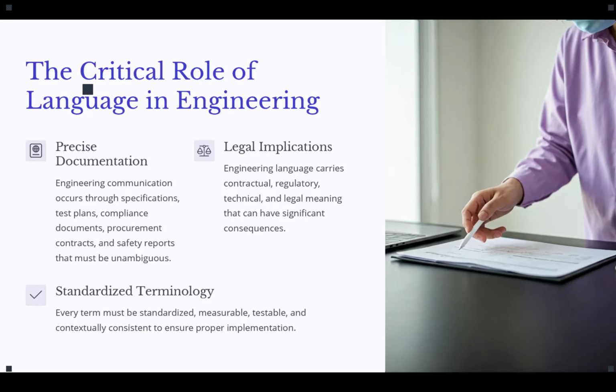Protective earth ground, which is intended to protect human safety, is one meaning. Another one is signal reference ground, which is critical for low noise electronic circuits, or chassis ground, which is bonding metallic frames to reduce electromagnetic interference, or EMI. And if you confuse those grounds, a system will malfunction, a safety hazard will occur, a compliance failure will happen, a contract could be invalidated.